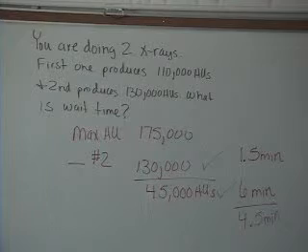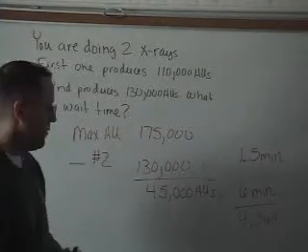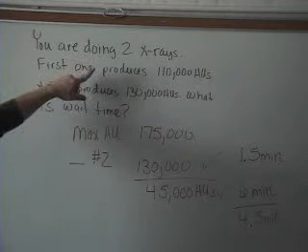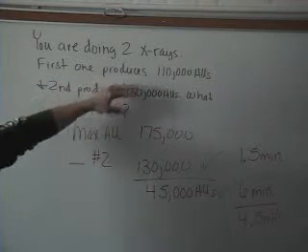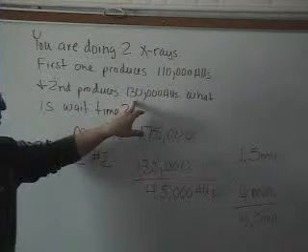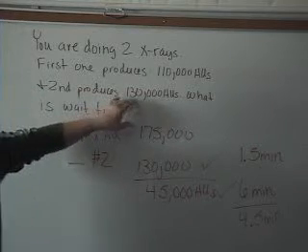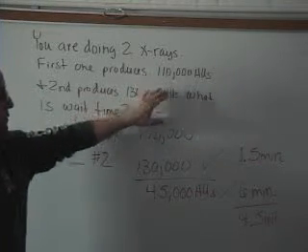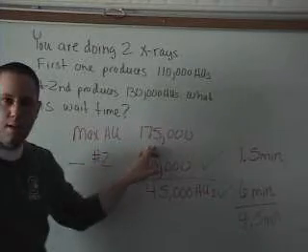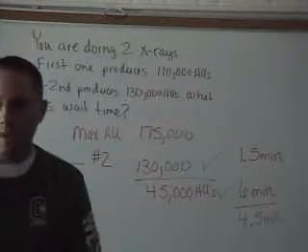This is an example of calculating the amount of time you wait from one x-ray to the other. You're doing two x-rays: one produces 110,000 heat units, the other produces 130,000 heat units. What is the wait time? The first thing you do is add these two together and see if they're more than the maximum. The maximum on the chart on page 81 is 175,000 heat units.